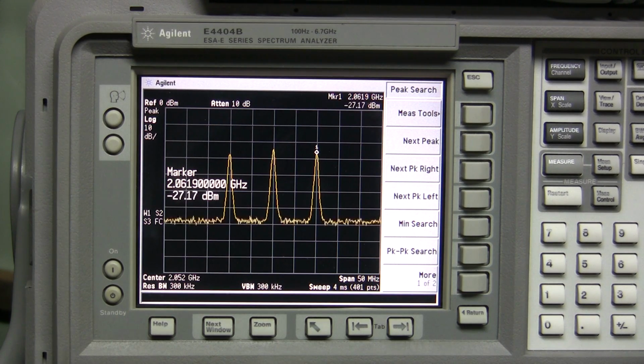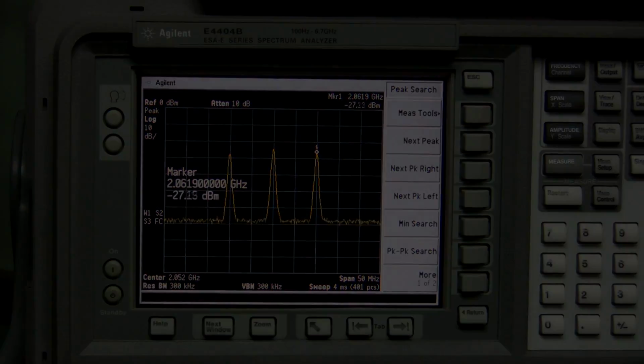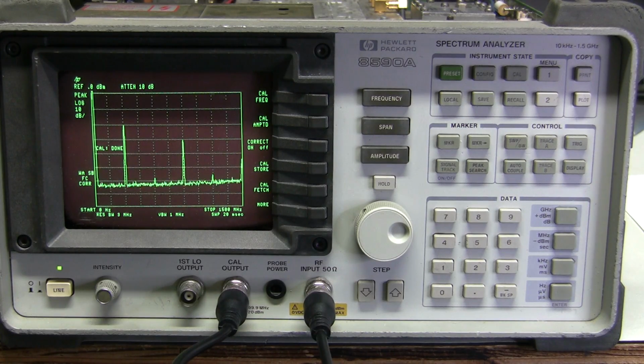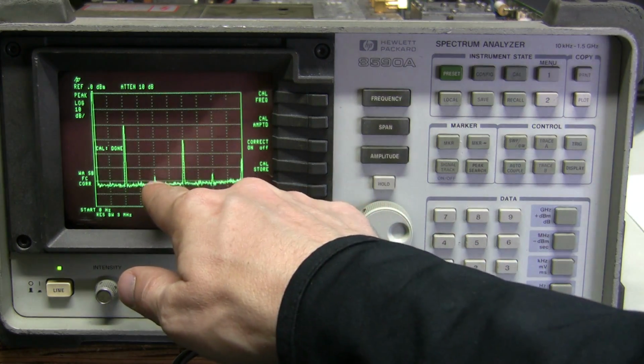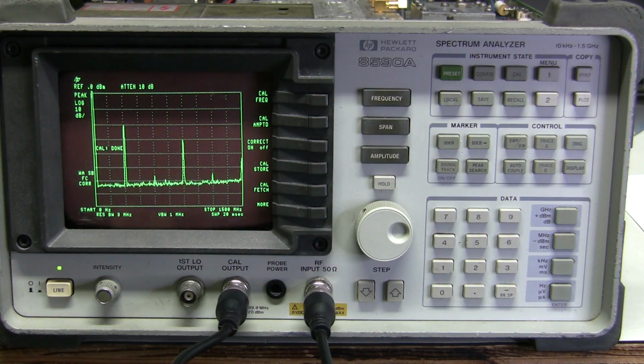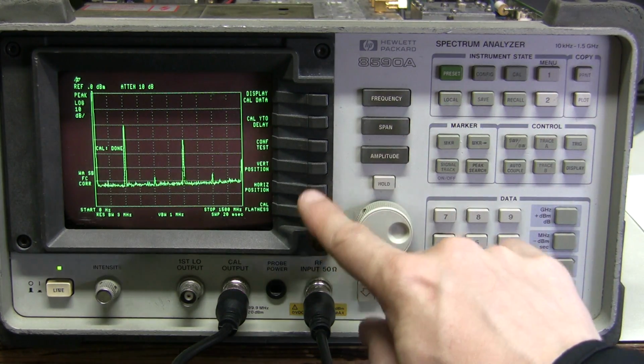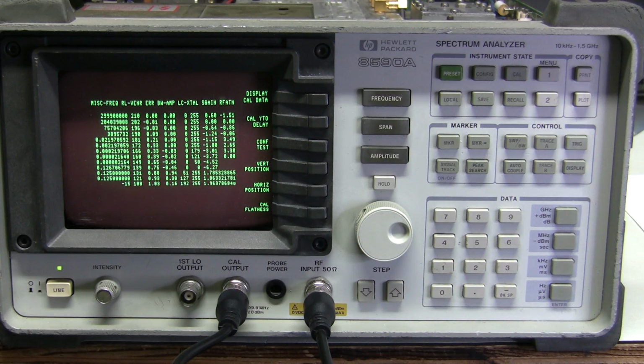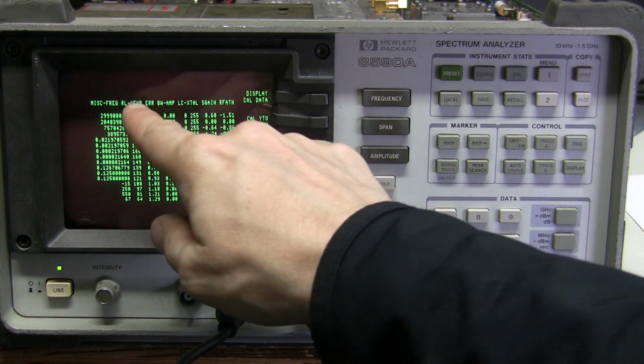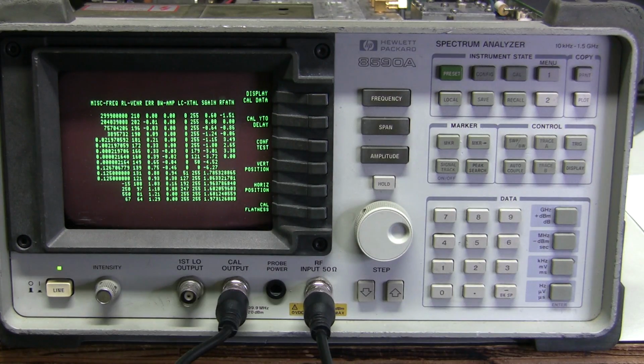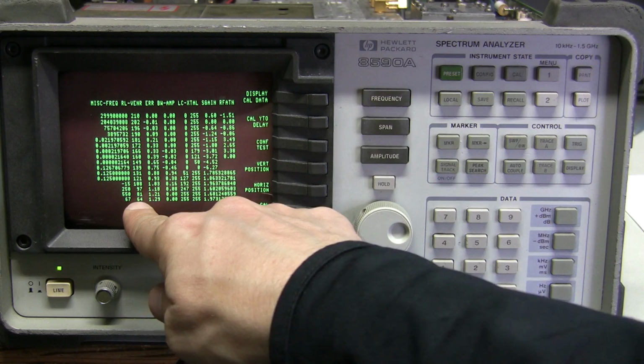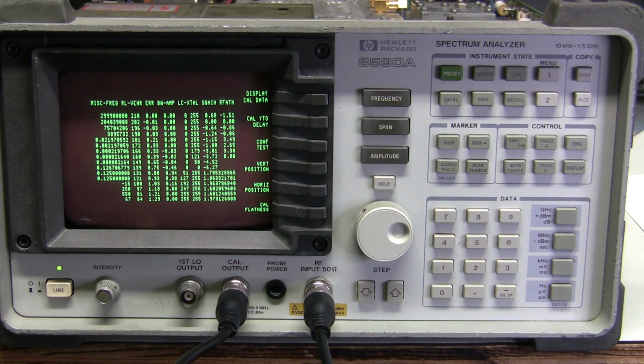But for now, let's see if the analyzer is gonna work with the fixed converter. It passes self-calibration now, and the result looks good at first glance, except that the second and fourth harmonics look a bit too low. Let's have a look at the calibration data. This column looks closer to what was suggested in the service manual. Still does not go as low as single digits, but certainly looks better.